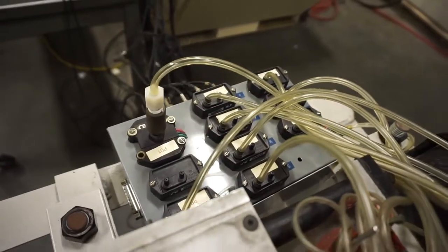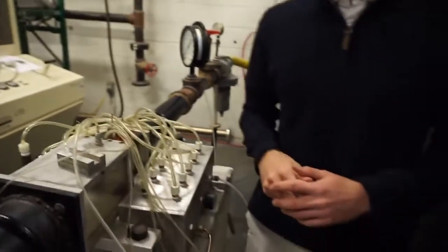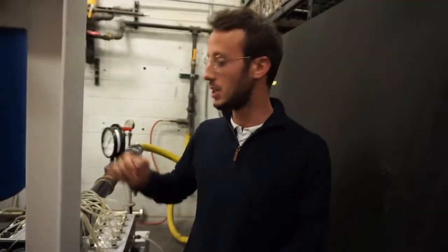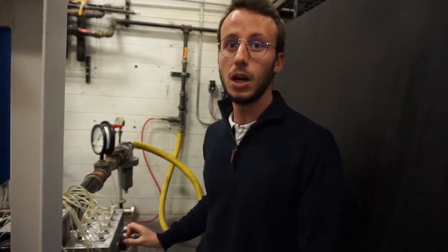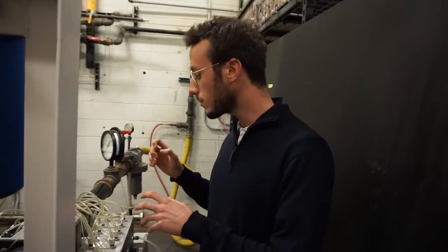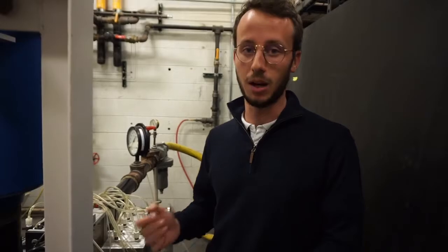The values you'll get in the calibration Excel file will be the voltage of each pressure transducer for each PSIG value from this pressure gauge. We'll show you only the print screens of each value, as the process for doing this calibration is pretty loud.